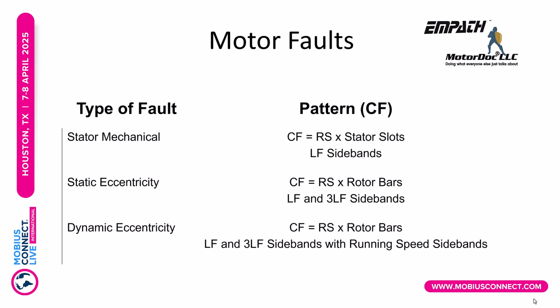So static eccentricity, same thing. That's going to be running speed times rotor bars. Line frequency, 3 times line frequency, sometimes 5 times line frequency sidebands. So 120 hertz in a 60 hertz environment between each one. Dynamic eccentricity has running speed around those static eccentricity sidebands. If I see both static eccentricity and dynamic eccentricity, it's called mixed eccentricity.